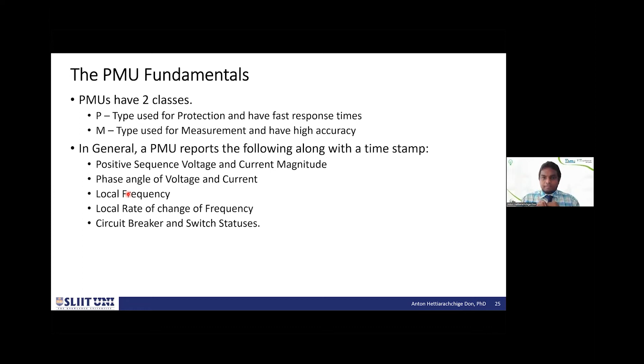This is how it's installed into the system. PMUs use the existing measurement infrastructure, the current transformers and voltage transformers already on the system, that's what they would use.